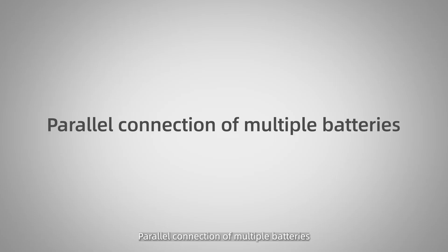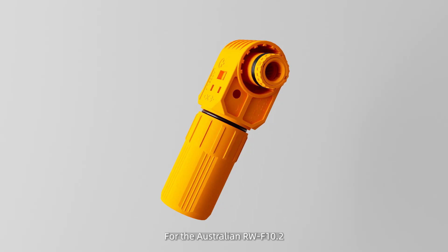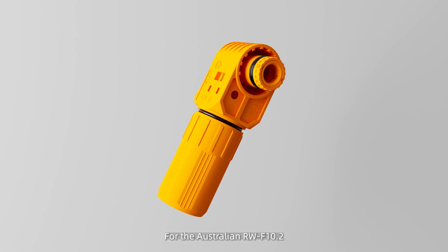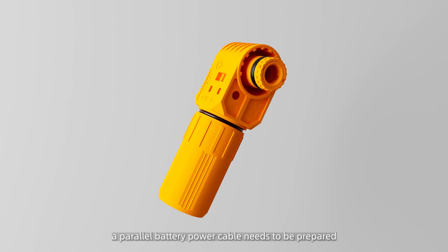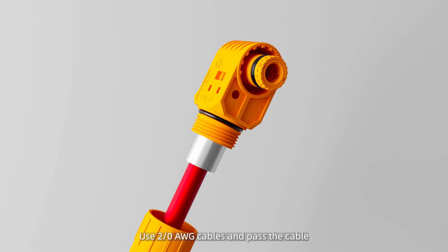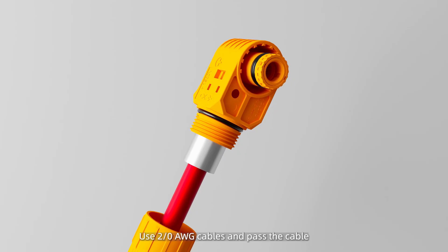Parallel connection of multiple batteries. For the Australian RWF10.2, a parallel battery power cable needs to be prepared. Use two zero AWG cables and pass the cable bundle through the plastic part of the connector.